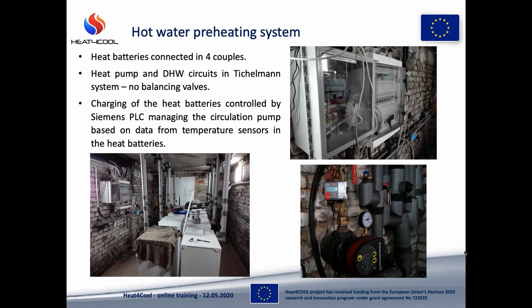The temperatures in the heat batteries and the charging are controlled constantly by the Siemens PLC. Based on the temperatures inside the batteries, the PLC decides whether there is a need to charge the batteries, and if yes, then the PLC turns on the circulation pump between the heat pump and the heat batteries.